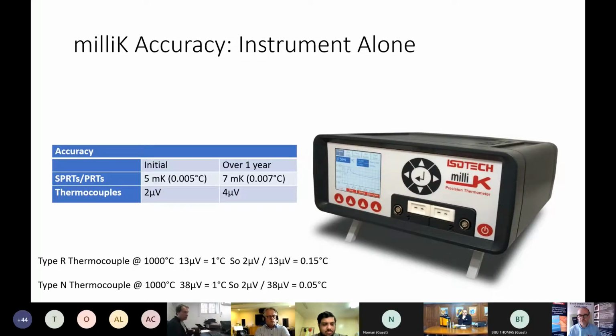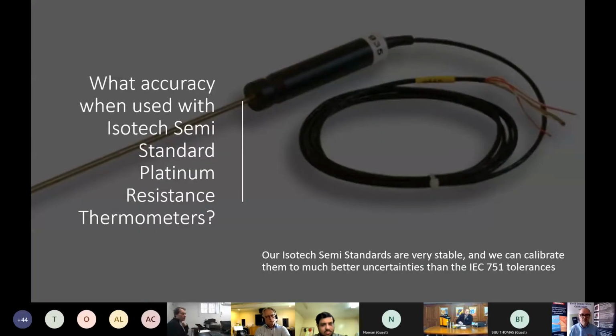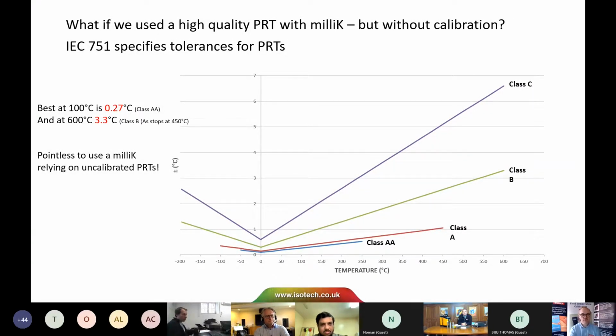So it's easy to understand the accuracy of the instrument, but how does that change when we have thermometers connected to it? What accuracy when used with Isotech semi-standard platinum resistance thermometers? Well, our semi-standards are very stable, and we can calibrate them to much better uncertainties than the IEC 751 tolerances. Let's see what they are. So this is from the standard for industrial PRTs, and it's not that great. At 100 degrees C, it's about 0.27 for the tightest class. If you go into 600 degrees, the standard only allows class B to go to that temperature, and its tolerance is 3.3 degrees.